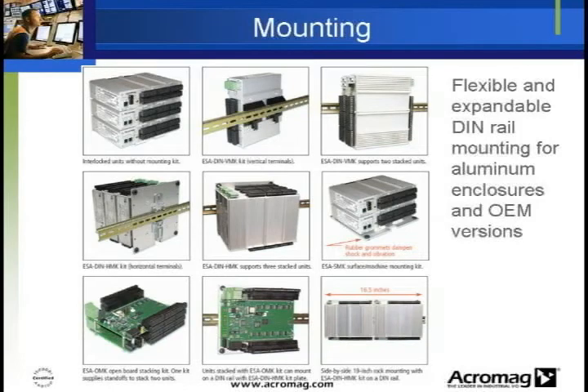Both the aluminum enclosure and the open circuit board are designed for efficient stacking and mounting to standard DIN rail systems and may be stacked either vertically or horizontally to take advantage of the high channel density for the most efficient use of space. With the ability to stack up to 3 tall and mount side to side, these EtherStax units provide combo analog channel density of up to 288 channels in just 16.5 inches of DIN rail space.